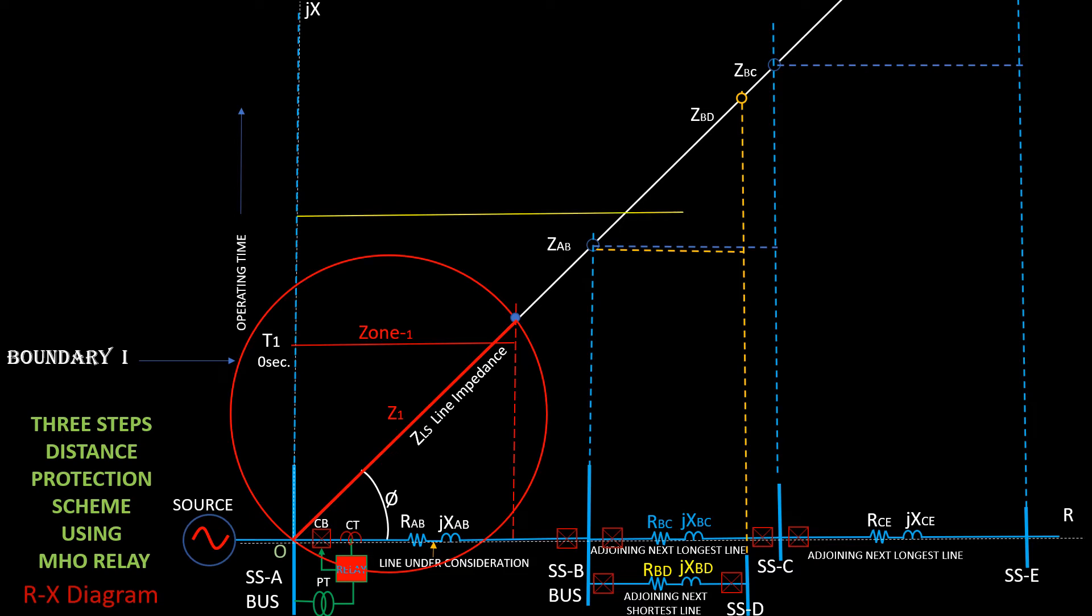Zone 2 protection is under the coverage of 100% of line between substation A and substation B plus 50% of adjoining shortest line, that is between substation B and substation D here.